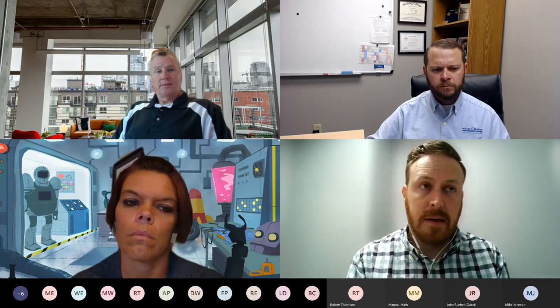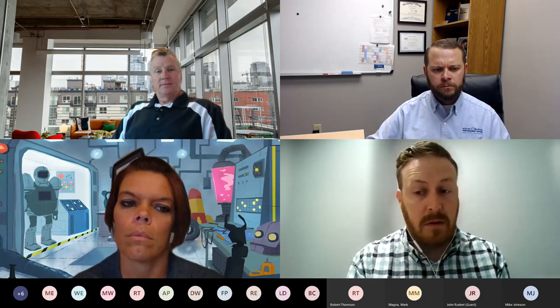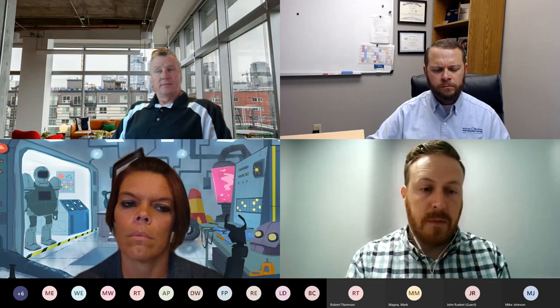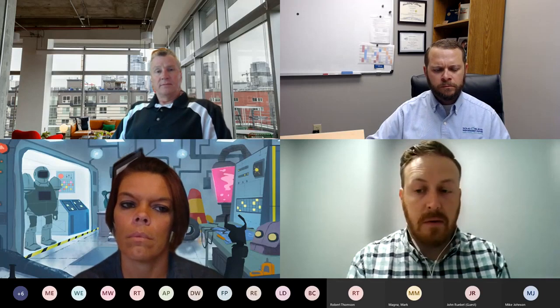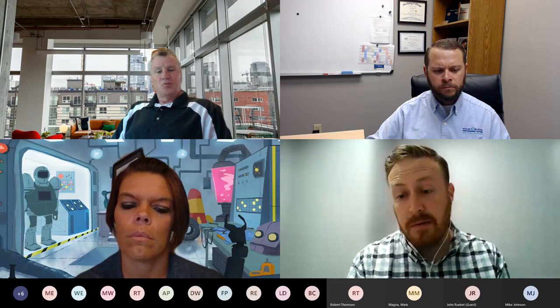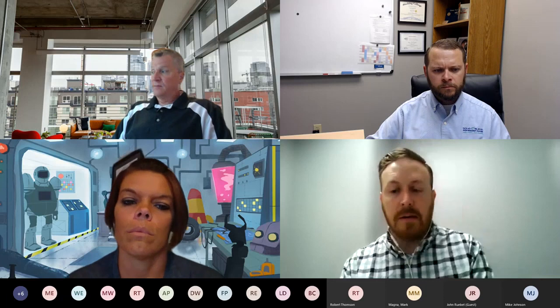Generally UVC in air handling equipment would be a lot similar to a T8 or T12 type tube bulb in the space. This type of light is not light that should be in the room, especially for periods of time. There will have to be safety measures in place for your equipment—if anybody's doing maintenance there, you wouldn't want that light on, because it wouldn't be good for their eyes or skin. Generally that's a tough thing to get by on the UV side, because it's a safety risk in another way.